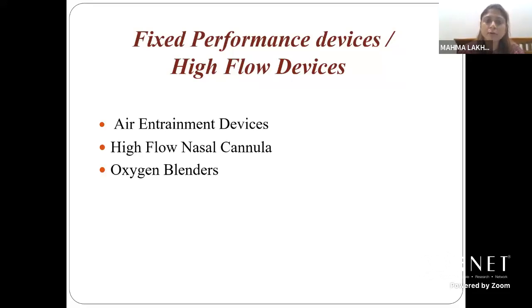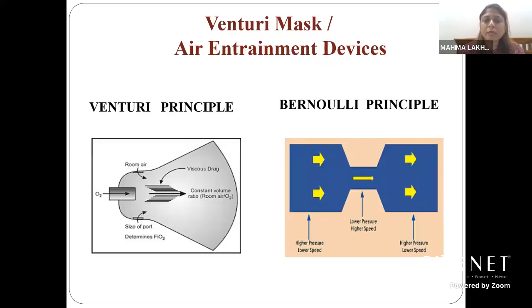Now we come to the fixed performance devices. Here we have the air entrainment devices, the high flow nasal cannulas, and the oxygen blenders. So air entrainment devices work on the Venturi principle or Bernoulli's principle. Here in the Venturi mask, the flow of oxygen is low, but it is made to pass through a very small orifice. So when it passes through a small orifice, as per the Venturi law, it produces a high velocity and a viscous drag. As you can see in the diagram, a viscous drag is created.